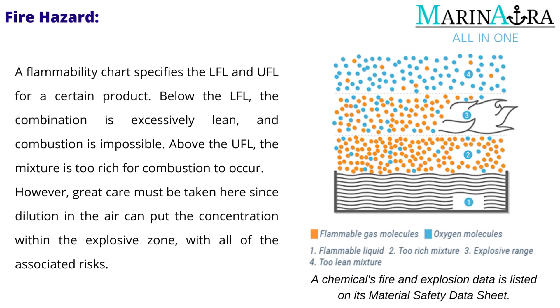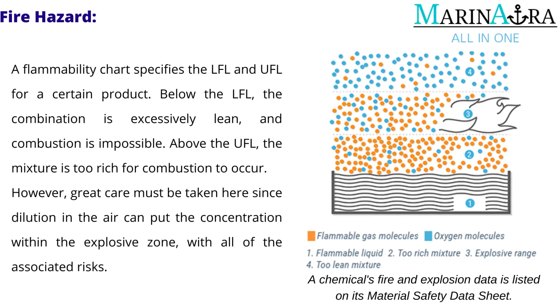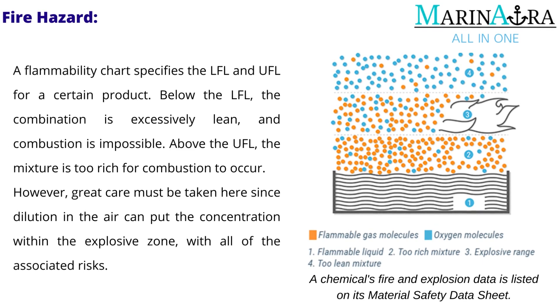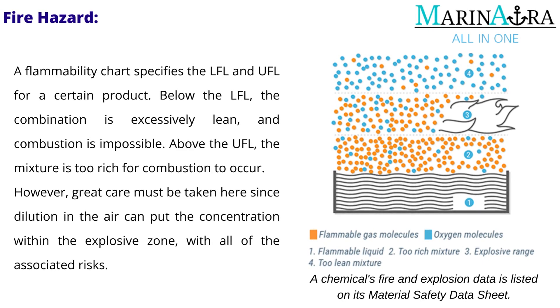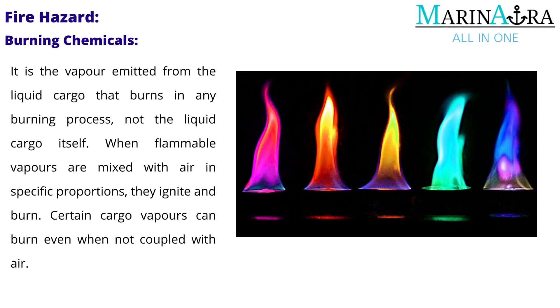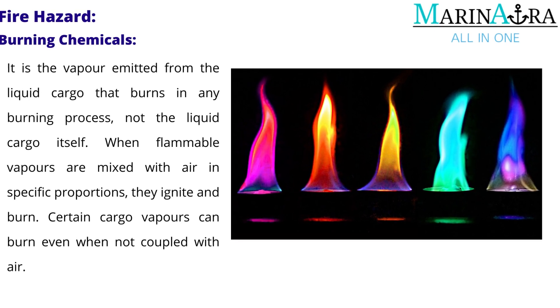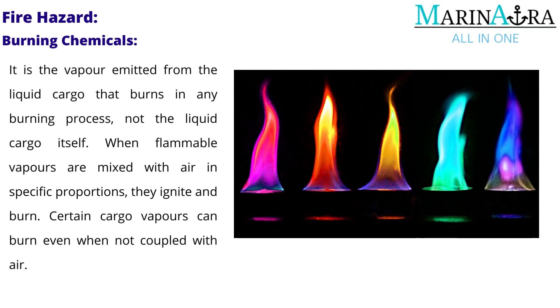A substance's auto-ignition temperature is the temperature at which combustion occurs without the input of external heat. A flammability chart specifies the LFL and UFL for a certain product. Below the LFL, the combination is excessively lean and combustion is impossible. Above the UFL, the mixture is too rich for combustion to occur. However, great care must be taken here since dilution in the air can put the concentration within the explosive zone. With all of the associated risks, a chemical's fire and explosion data is listed on its material safety data sheet.